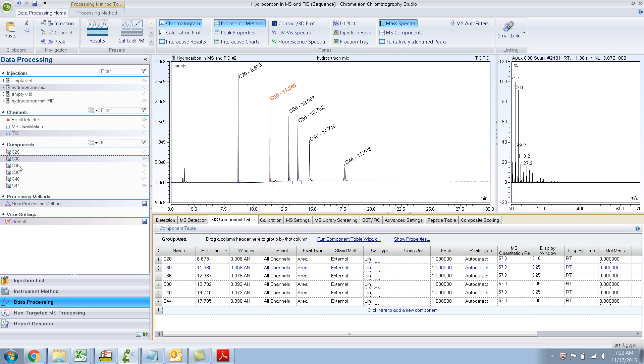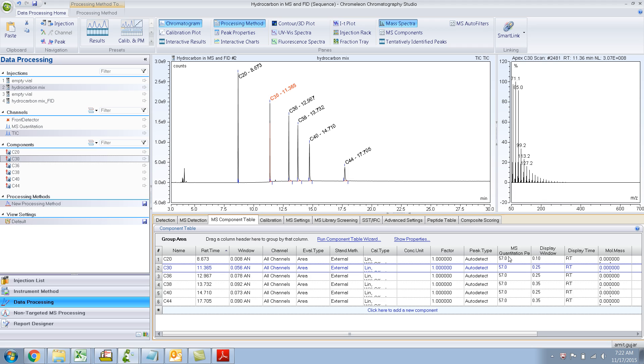So it could not find the reference peak - that is, it could not find ion 57. Ion 57 is our MS quantitation peak. At first, when I was doing this for the first time, it was very surprising why it could not find it. I mean, it seems so obvious, right? I put in the right retention time and windows and everything, and still it could not find it.